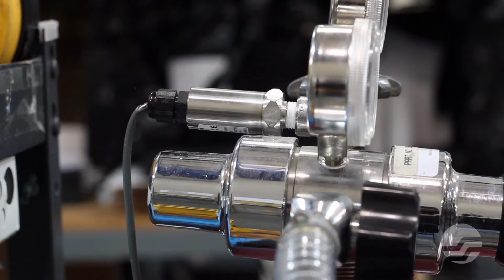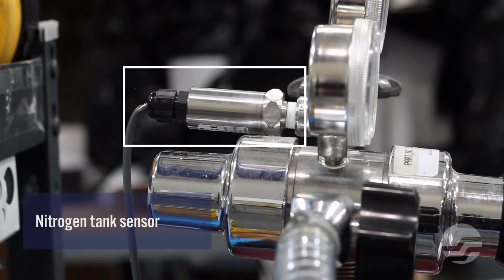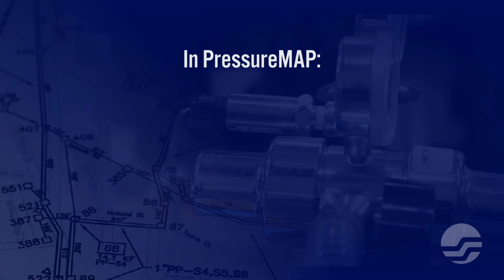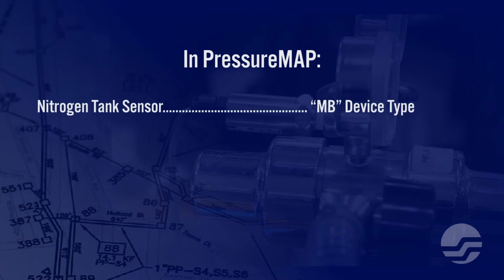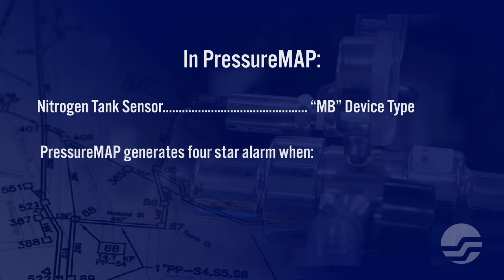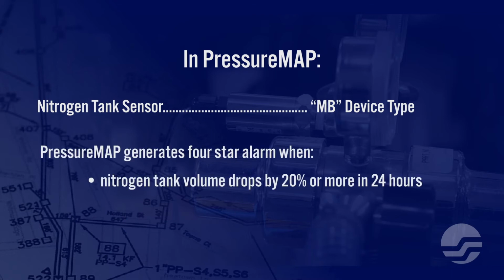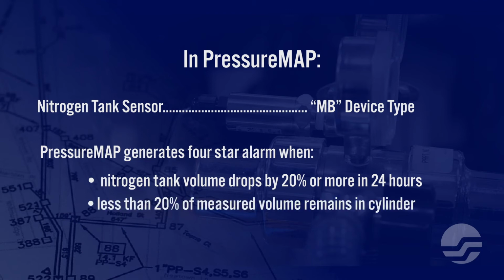The System Studies nitrogen tank sensor can be screwed into the fitting on the high pressure side of the nitrogen cylinder regulator. The nitrogen tank sensor is wired to the TD termination point of the UM260. The nitrogen tank sensor is entered into Pressure Map as an MB device type. Pressure Map will generate a 4-star alarm when the nitrogen tank volume drops by 20% or more in a 24-hour period, or when less than 20% of the measured volume remains in the cylinder. This gives technicians time to resolve the situation before your system suffers a catastrophic loss of pressure.